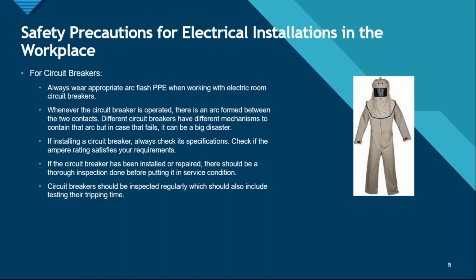If installing a circuit breaker, always check its specifications, always check its current rating, and check if the ampere rating satisfies your requirements. If the circuit breaker has been installed already or repaired, there should be a thorough inspection done before putting it in service condition. For a circuit breaker as well, whenever regular testing and maintenance is happening, the tripping time of the circuit breaker should also be checked. Circuit breakers should be inspected regularly, which should also include testing their tripping time.